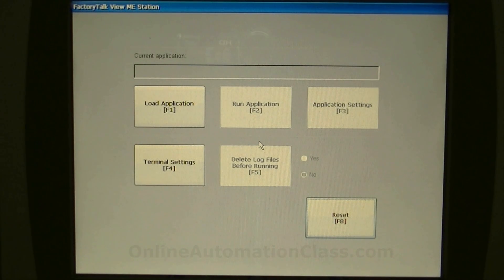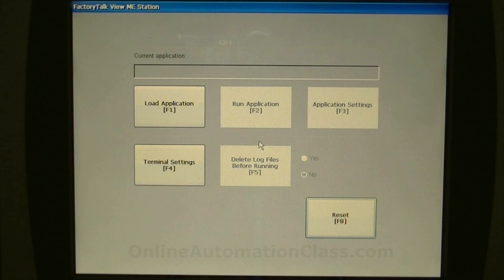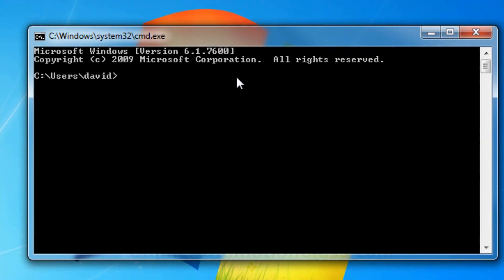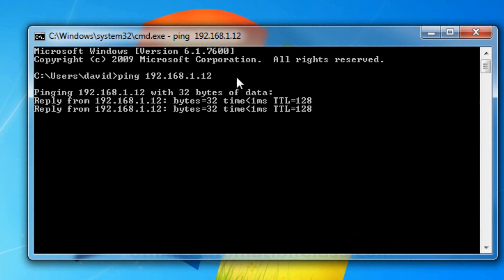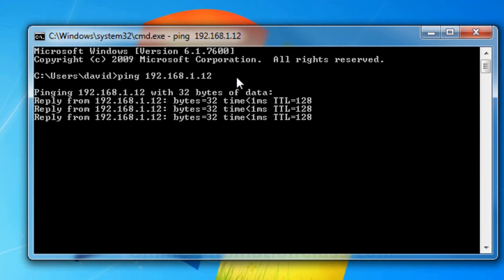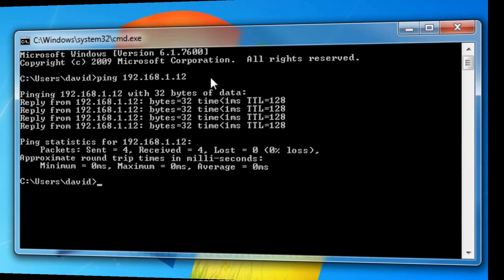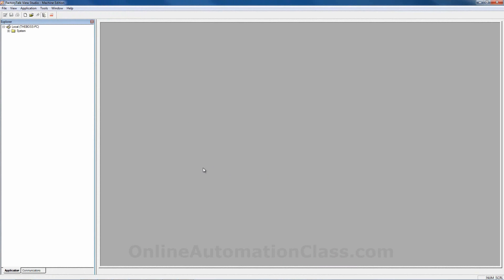After restarting the terminal, the communication link between the PC and the terminal is verified by pinging the terminal's IP address from the PC. At this point, RS-Linx Enterprise in Factory Talk View Studio should be able to see the terminal.